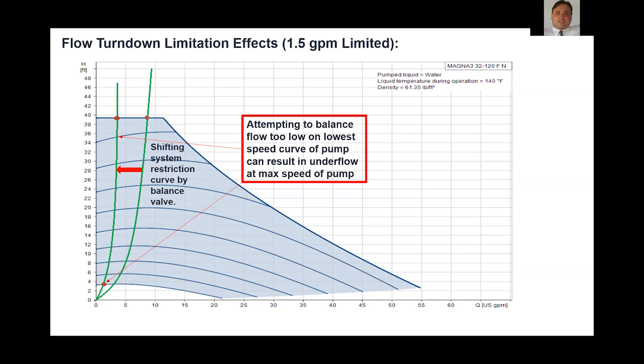So oftentimes with more advanced solutions, not only is the pump a variable speed pump, but you may have two different balance positions with, say, a three-way diverting valve with different balance positions that have to be set in the field, and then controls integrated with that, so that when you need to get to those lower flow turn downs under those cold ambient conditions, you can achieve that with basically two balanced system restriction curves. So you're toggling back and forth at those cold ambient conditions to hit those specific low flow turn downs that are required. So those are things that have to be thought about as part of the application. And again, this is why it's important to make sure the manufacturer's involved and their controls and their solutions are being applied with the product so that it can achieve those discharge water temps at all times.